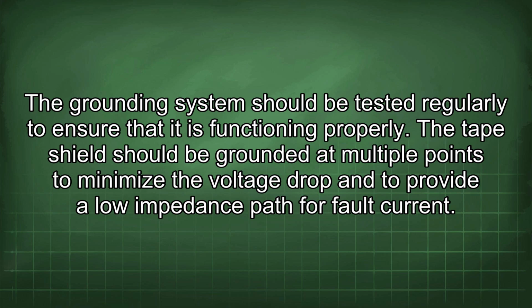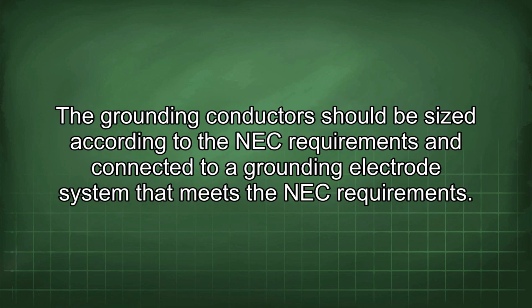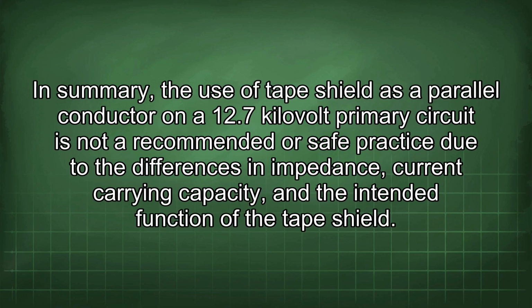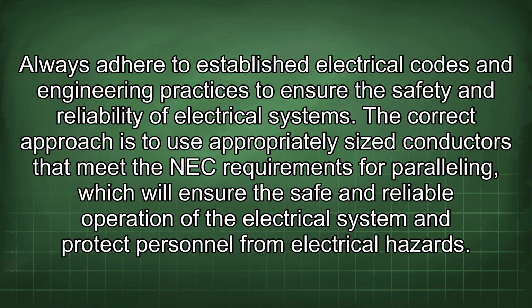The tape shield should be grounded at multiple points to minimize the voltage drop and to provide a low impedance path for fault current. The grounding conductors should be sized according to the NEC requirements and connected to a grounding electrode system that meets the NEC requirements. In summary, the use of tape shield as a parallel conductor on a 12.7 kilovolt primary circuit is not a recommended or safe practice due to the differences in impedance, current carrying capacity, and the intended function of the tape shield. Always adhere to established electrical codes and engineering practices to ensure the safety and reliability of electrical systems.